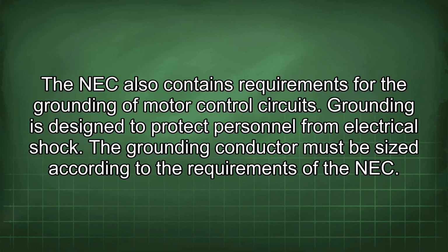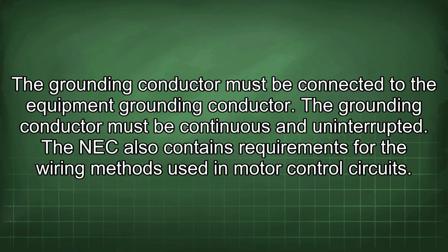The NEC also contains requirements for the grounding of motor control circuits. Grounding is designed to protect personnel from electrical shock. The grounding conductor must be sized according to the requirements of the NEC. The grounding conductor must be connected to the equipment grounding conductor. The grounding conductor must be continuous and uninterrupted.